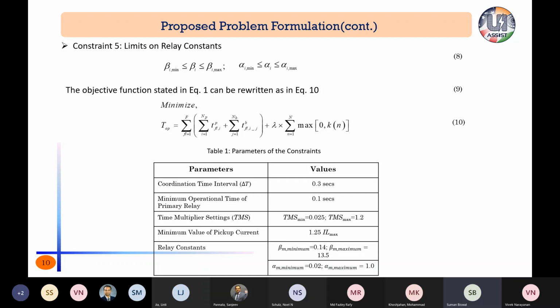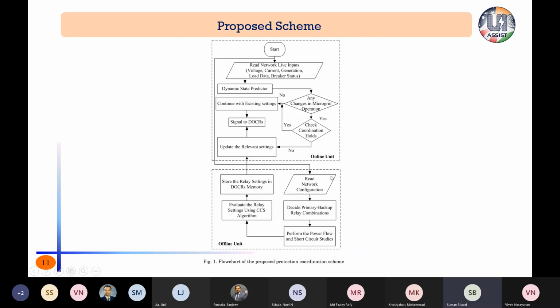So whatever may be the normal current flowing, based on that, we have multiplied with a factor of 1.25. So this gives us the pickup setting value for our case. And also the bounds on the relay constants are specified. And this is our proposed scheme.